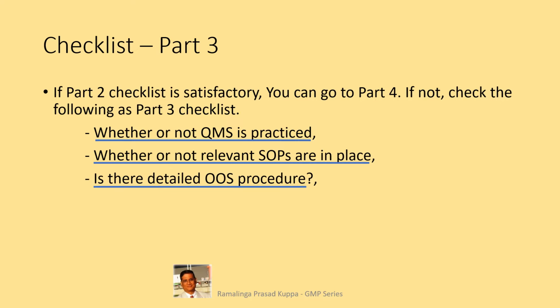Is there a detailed OOS procedure? The OOS procedure should be detailed as per CDER guideline and MHRA guide. Most of the places OOS procedure is paraphrased from the guideline. It is difficult to execute on benchtop investigations. The OOS procedure should be descriptive in imperative mandatory style. The sentences should be assertive with actual action required during investigation.